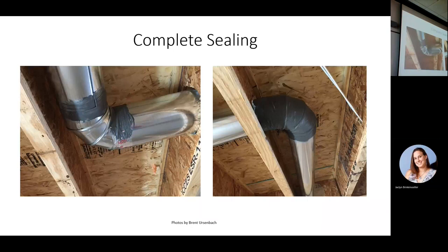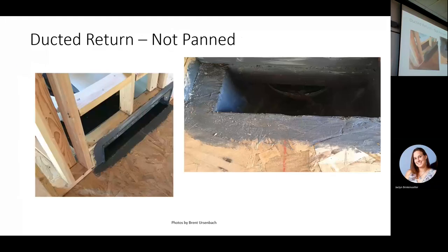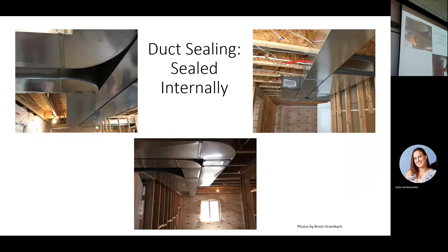Oh, nice. These leak just as much as the crimps, just about. This guy did a good job. He sealed, and this one is when they ducted their returns. You see they have a sheet metal boot coming up, and then they've sealed that up. And this is the one where they sealed internally. I walked down in there and I said, wait a minute, I don't see any duct sealer. And then they had a sticker on the furnace.